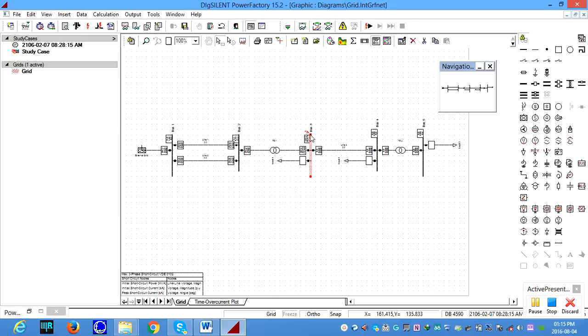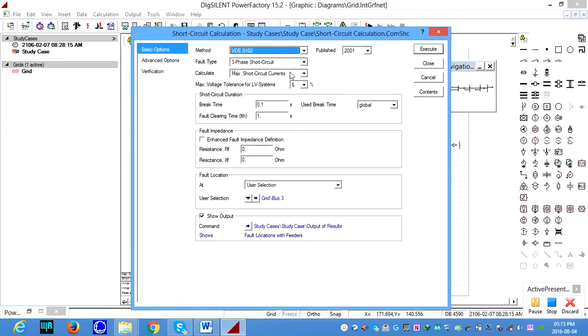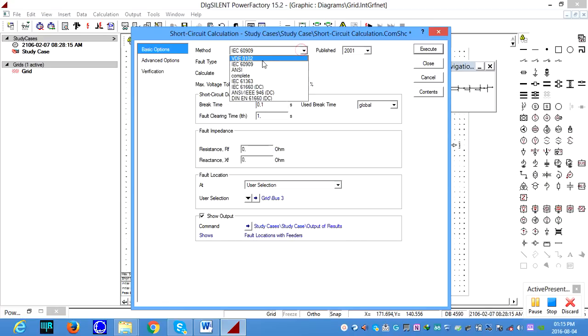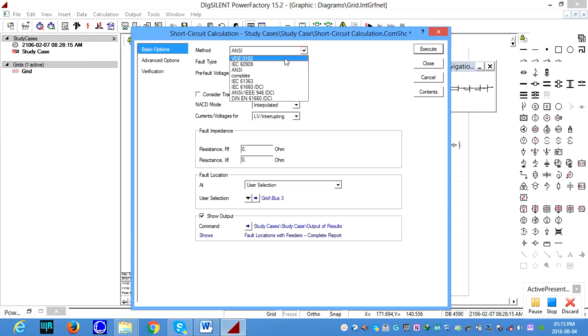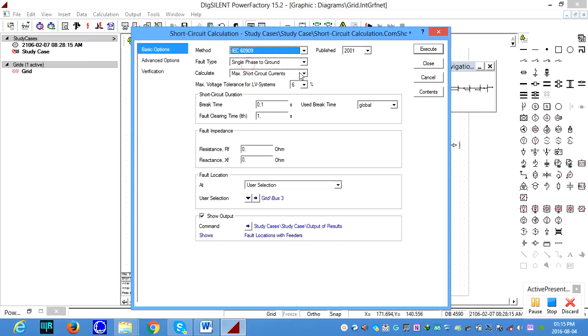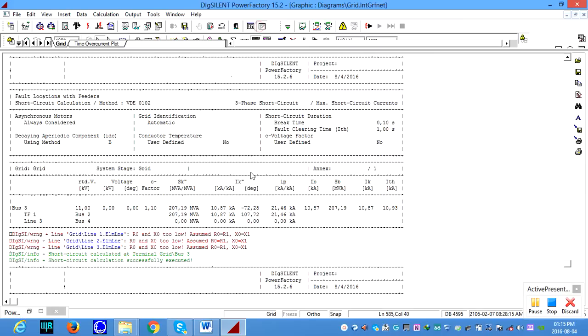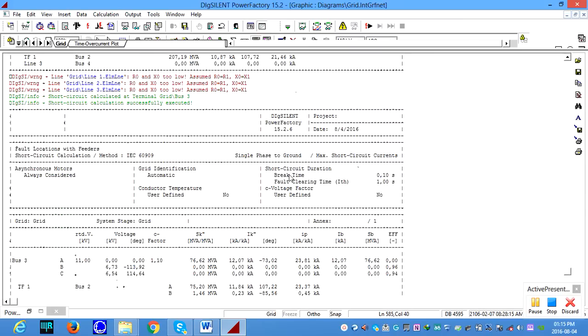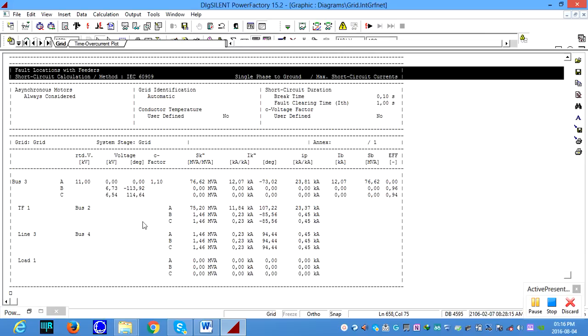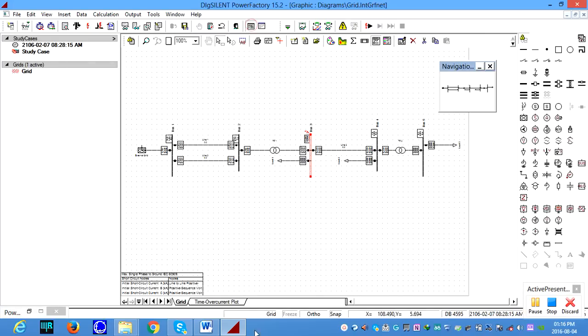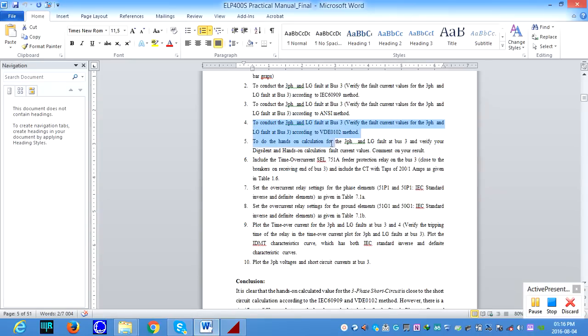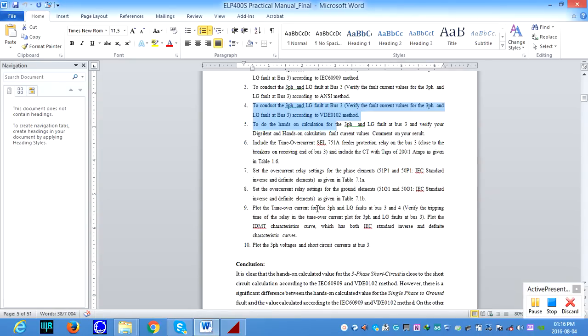Next, we need to apply a different line to ground fault. Let's say instead of this one, you can select single line to ground fault, single phase to ground fault, and you can use the IEC method or the ANSI method, it doesn't matter. Let's say we are using the IEC method and we can apply the fault, and you can validate your IEC method. You applied a single phase to ground fault, and you can see the results. Okay, so these are the parts they're speaking about: different types of short circuit, the ANSI method, and everything you have done. And also you need to include your ANSI calculations.